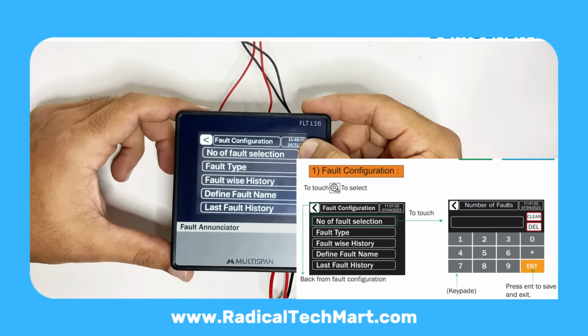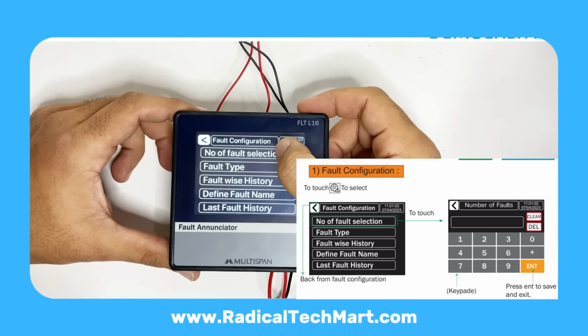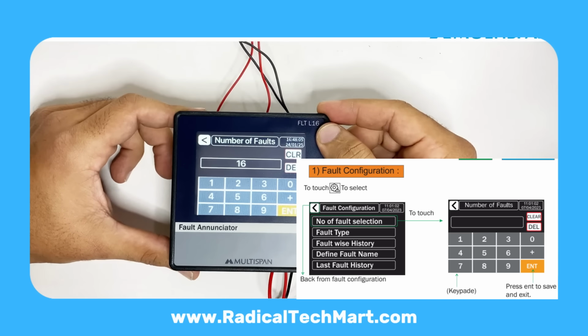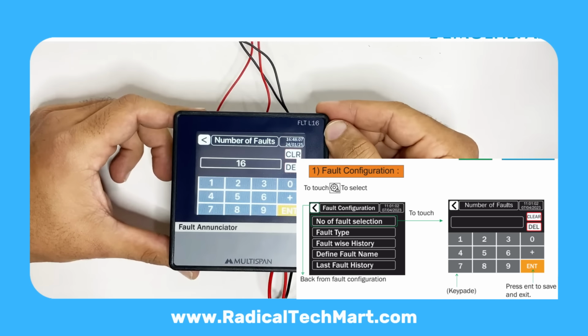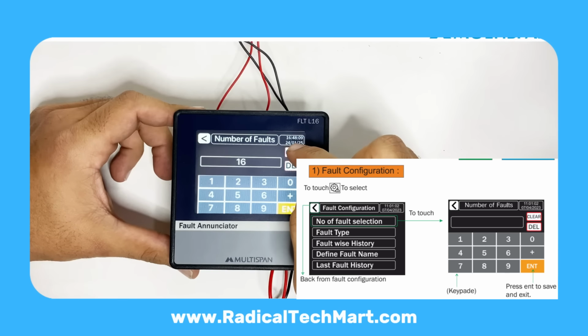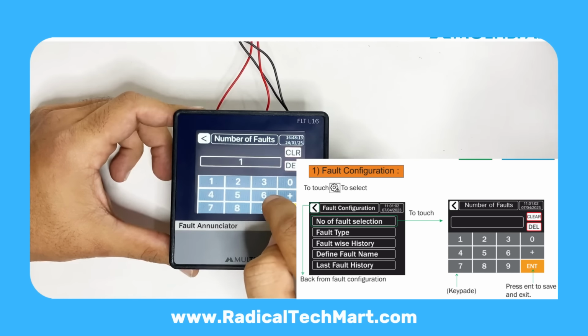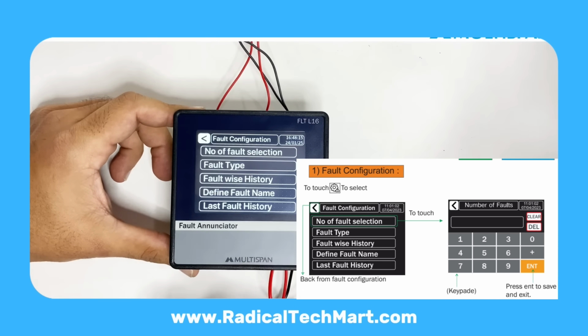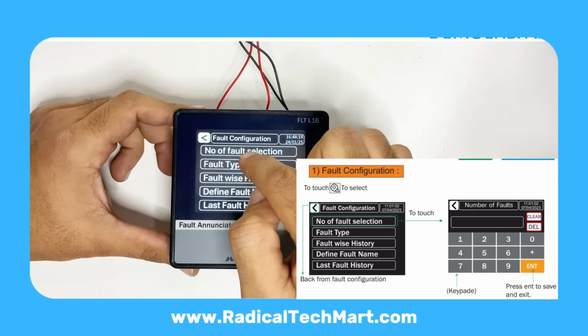Inside fault config, the first option is number of faults. Open this and you can decide how many faults you want to use. For example, if you only have 10 active faults in your system, you can clear the default and enter 10. Then, on the main window, only fault 1 to fault 10 will be displayed.